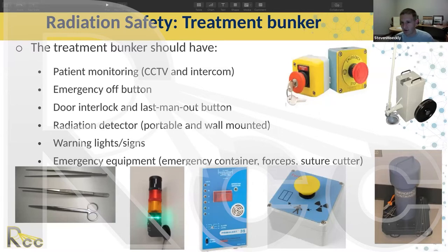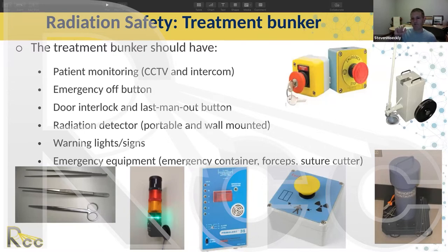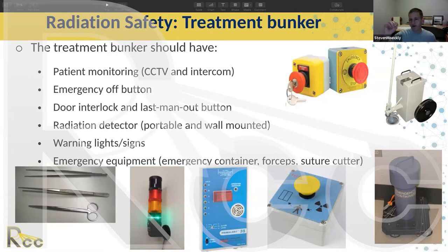The last man out button is a button that must be clicked before you can initiate treatment. The idea is that the last person leaving the room will click that button — it means they've looked around and confirmed they are the last person leaving the room.